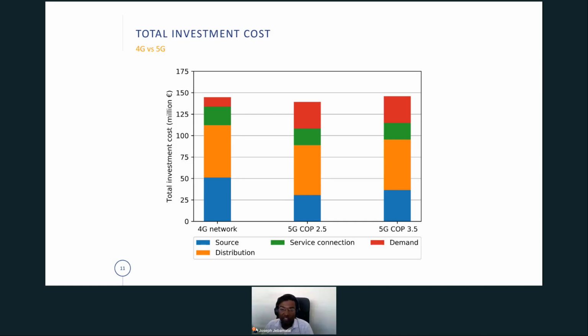So now let's compare how the cost pans out between these scenarios. If you look into the 4th generation systems, we have the source cost here, which is in blue, and then we have the distribution network cost, and then we have the heat exchangers in the building cost. These are the 4th generation costs. And then if you look into the 5th generation cost, the source cost is a bit lower because we require less thermal energy. And then the distributed heat pump cost is taken into account on the demand side. So we have a higher cost on the demand side.